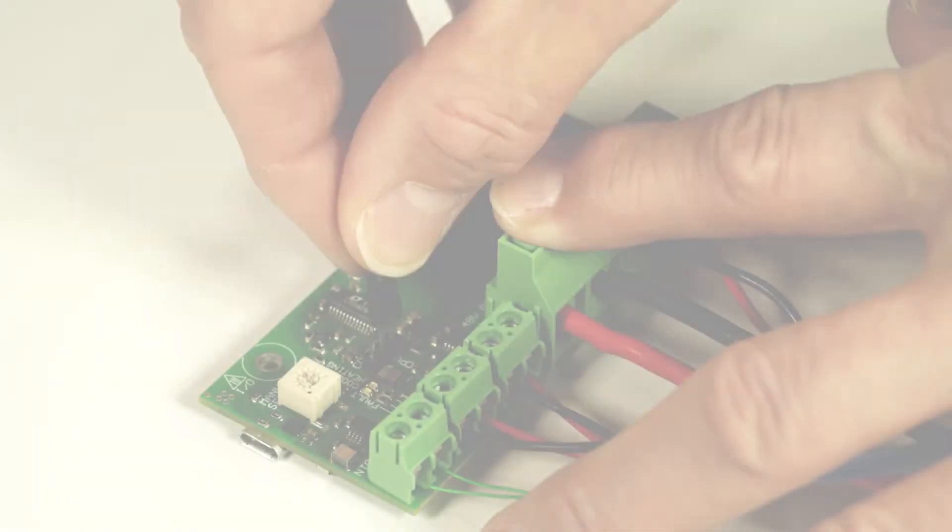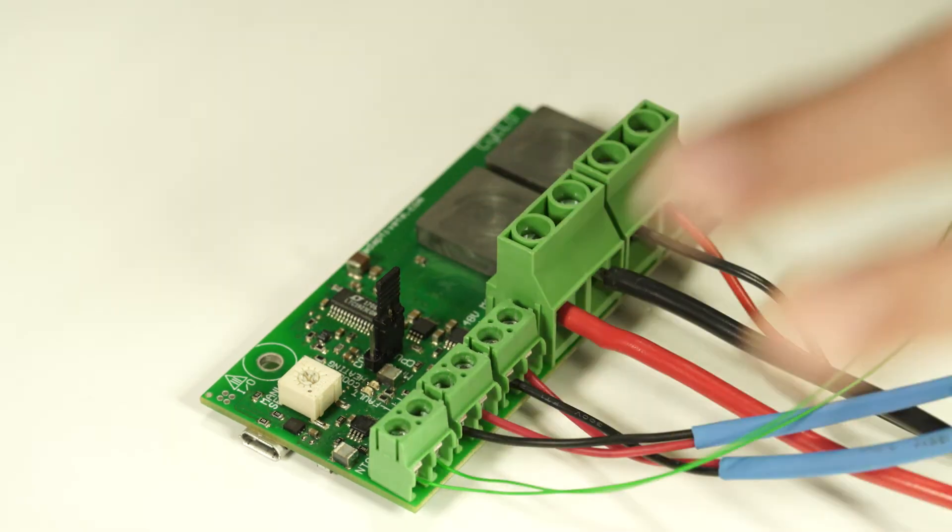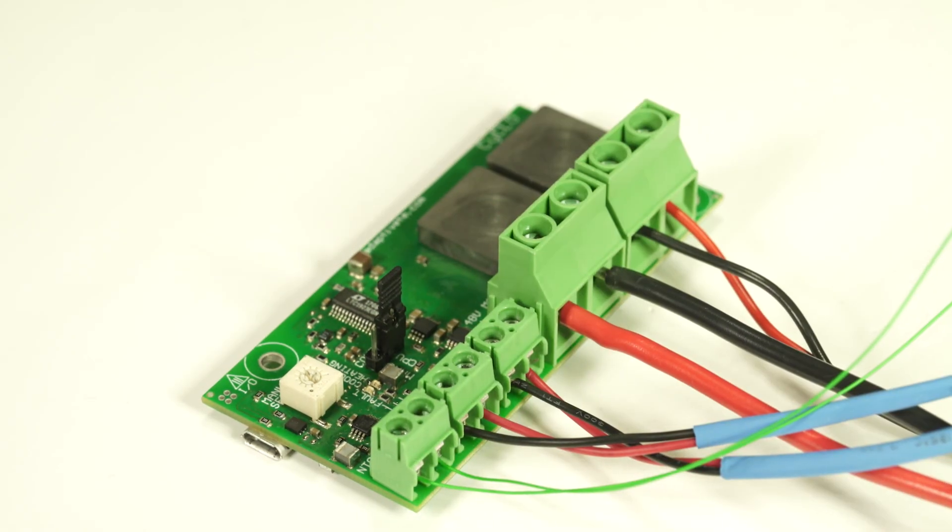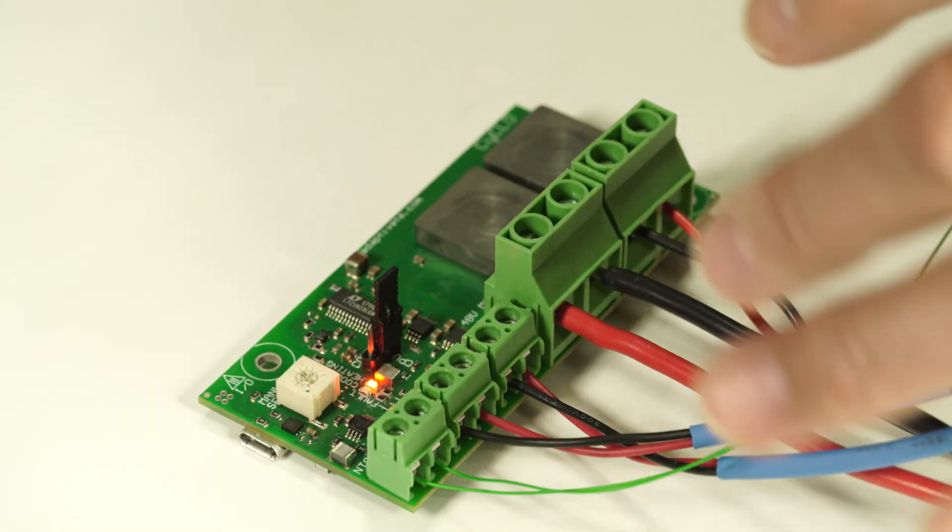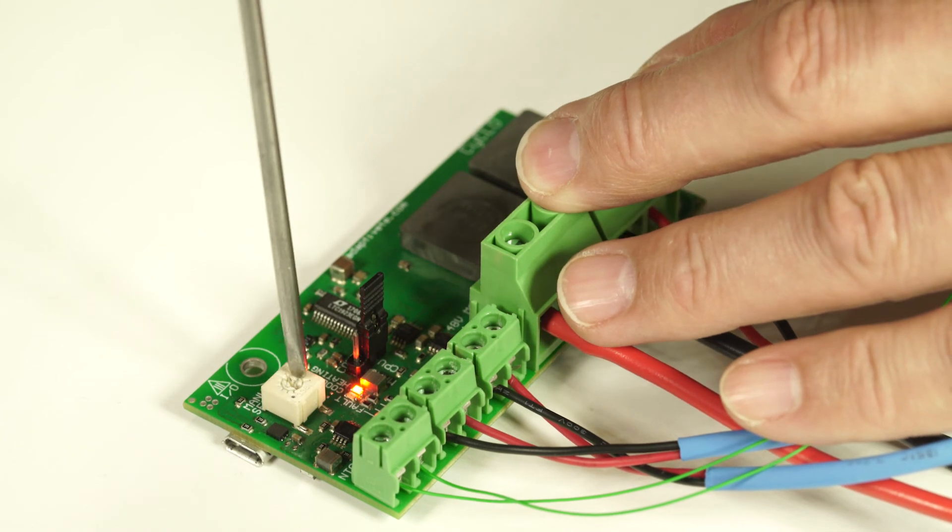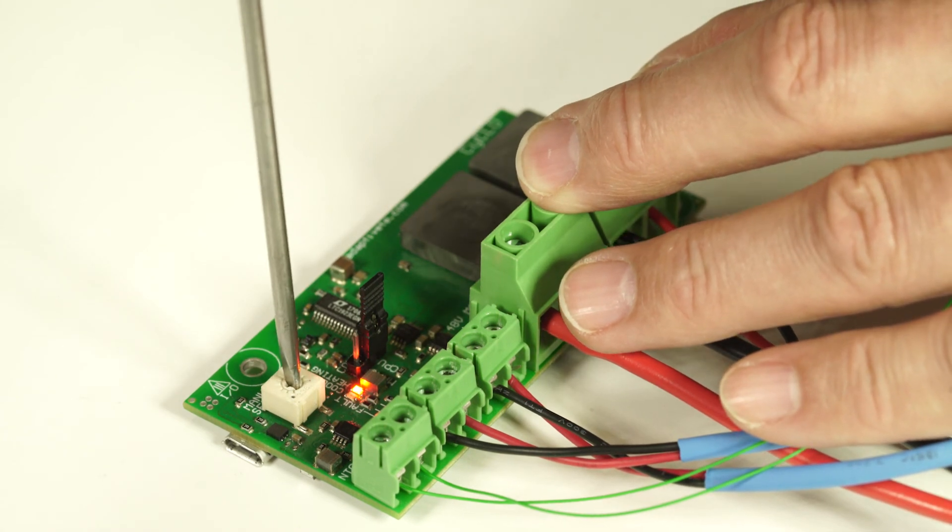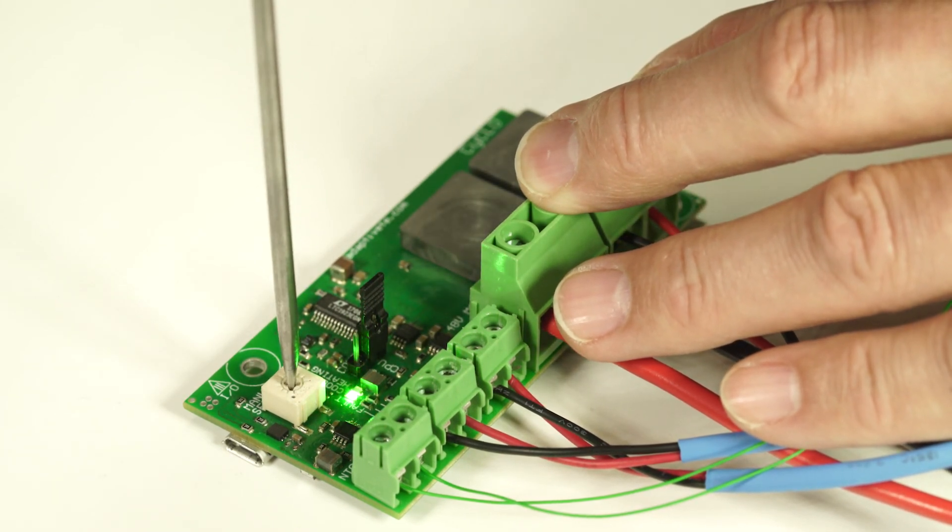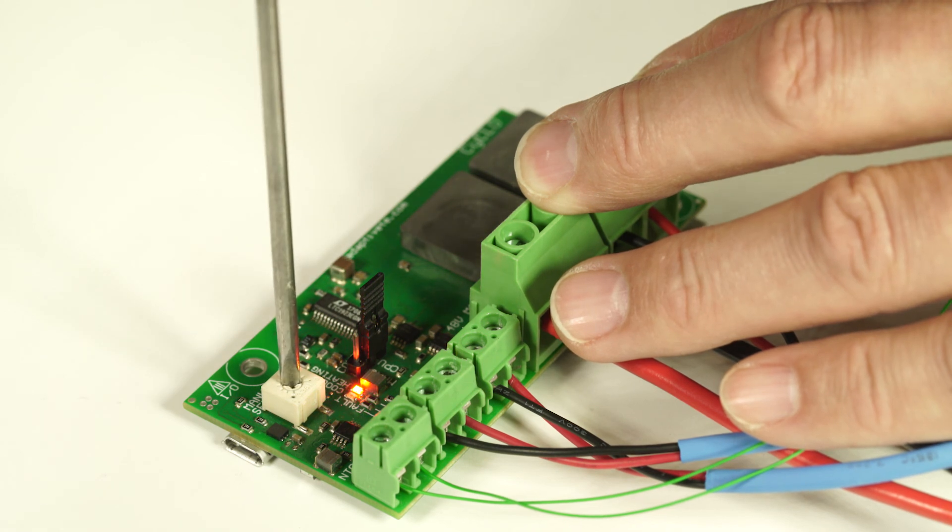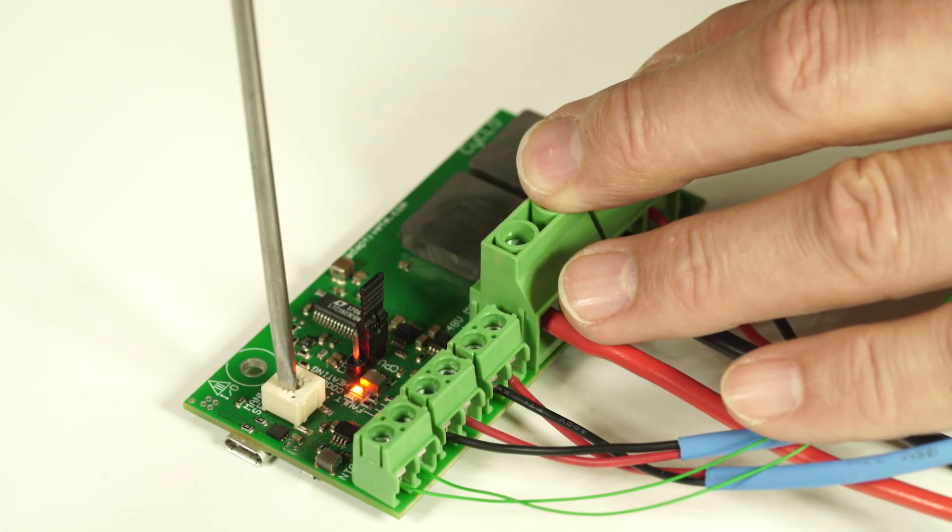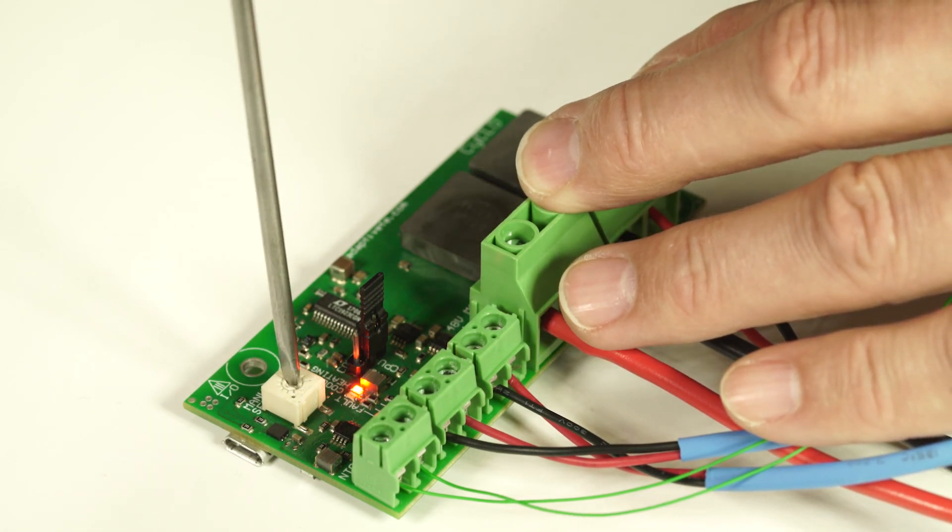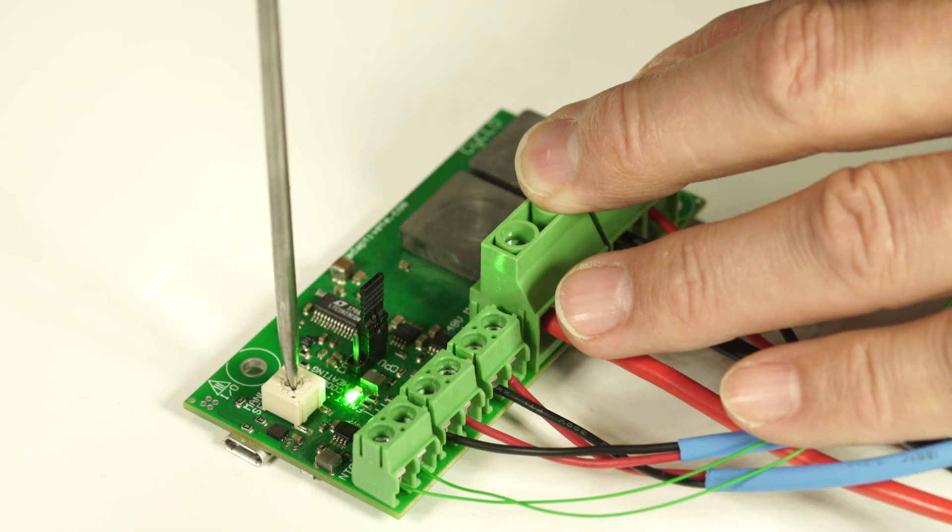To use the Cyclo in manual mode, set the jumper to manual. This allows you to set the set point to heat or cool within predetermined limits. Anti-clockwise for cooling, clockwise for heating. The LEDs will give feedback by changing to red for heating and to green for cooling.